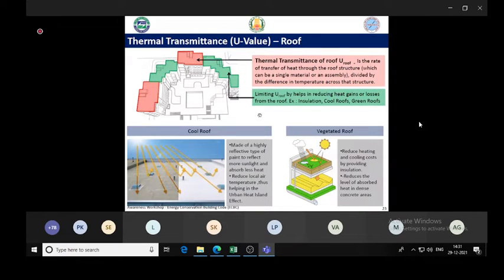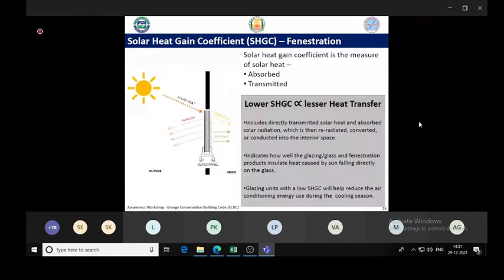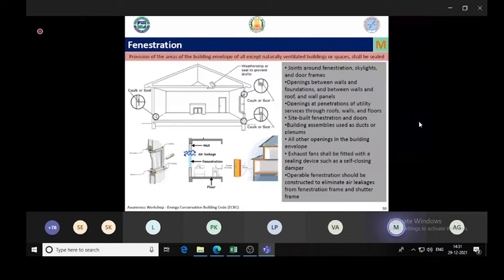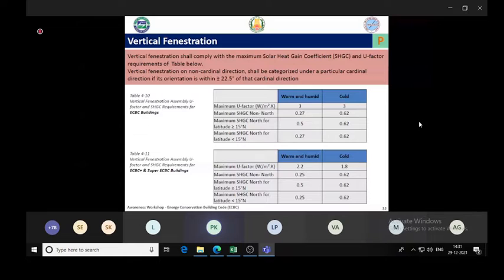Yes. Now, moving on to the roof. In roof, we have two requirements. One is the U value of the roof, which deals with the direct heat transfer, and then we have the cool roof requirements. The U value of the roof, as per the code, is restricted to 0.33. Here again, a conventional roof U value is going to be around 2 to 2.5.